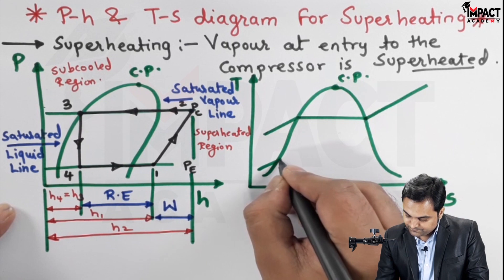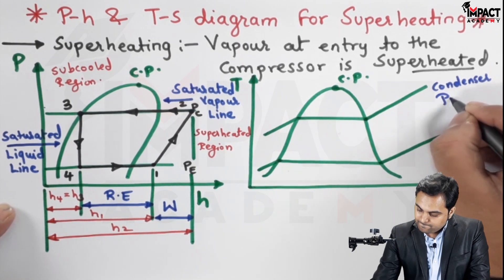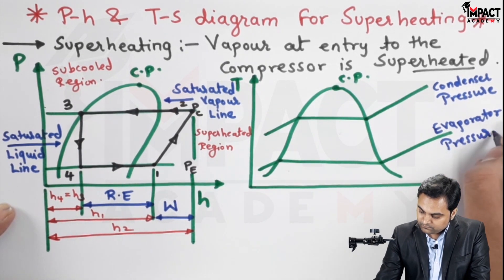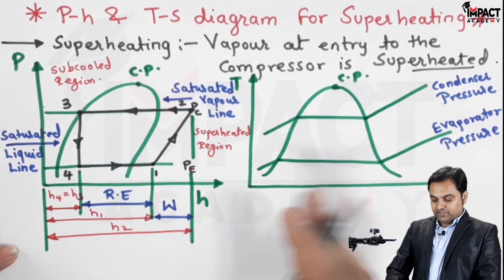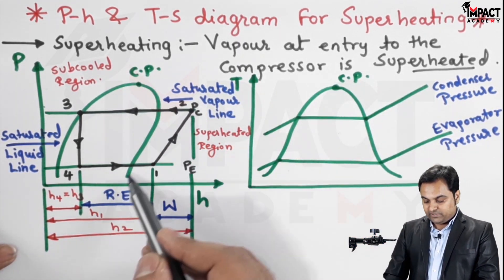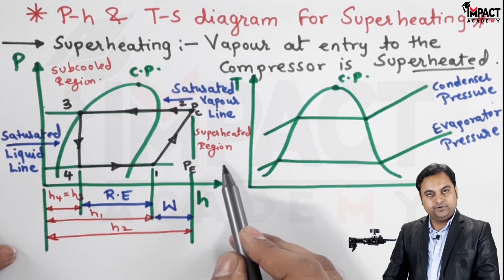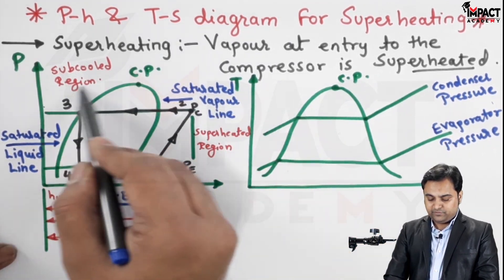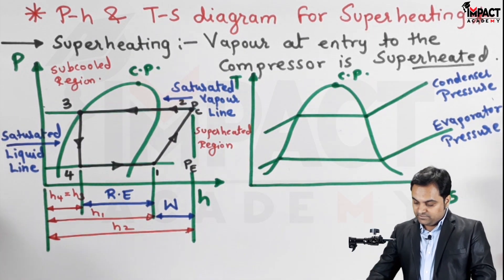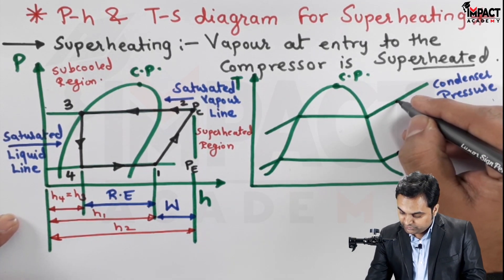Drawing two constant pressure lines on the T-S diagram: the higher pressure is condenser pressure and the lower pressure is evaporator pressure. Similarly to the P-H diagram, the saturated liquid line is on the left and saturated vapor line is on the right. The superheated region is to the right of the saturated vapor line, and the sub-cooled region is to the left of the saturated liquid line. Point one is plotted in the superheated region, and compression is isentropic so entropy remains constant.